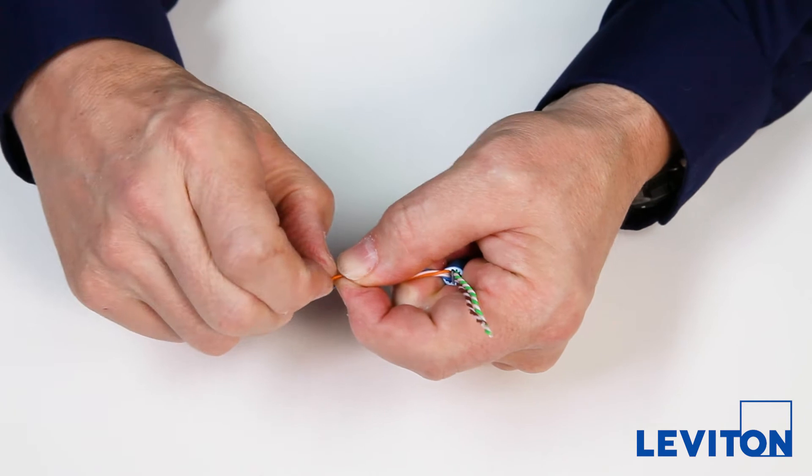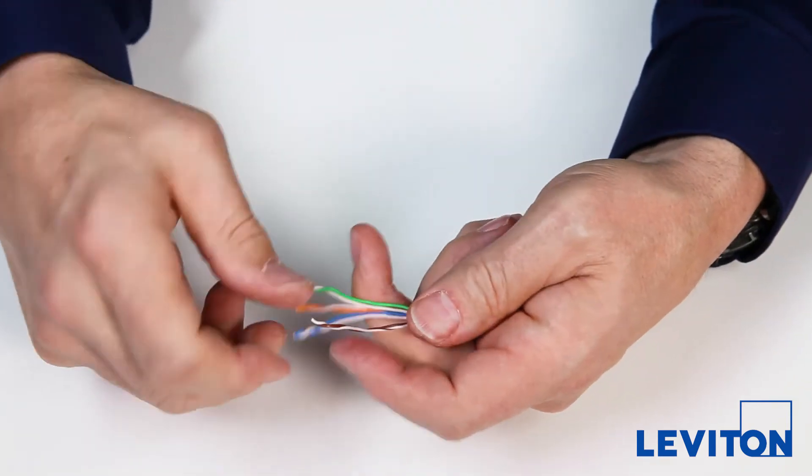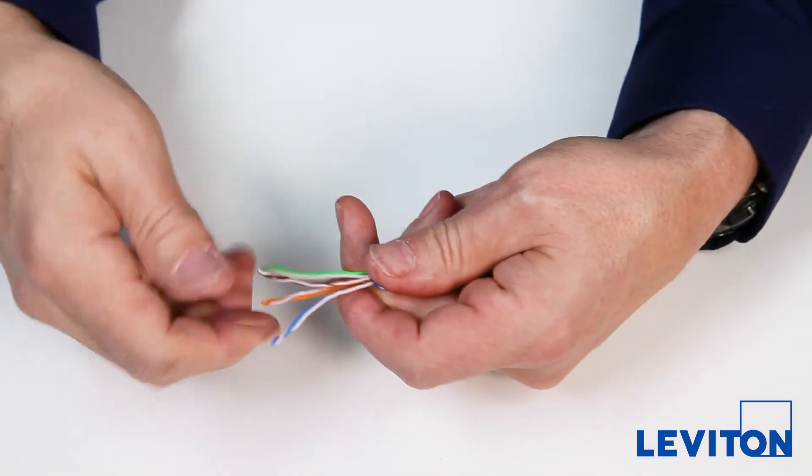Don't drag a tool along the conductors to straighten them, as it can flatten and distort the conductors, affecting the transmission quality of the cable.